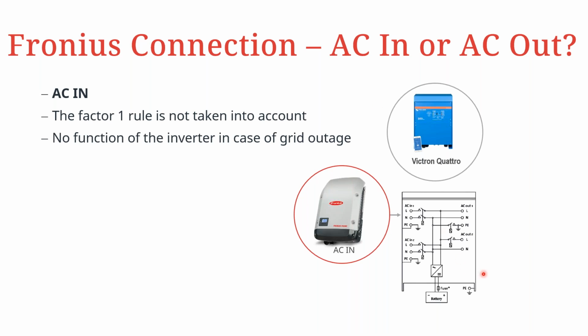So when it comes to the connection of the Fronius inverter to the Victron inverter, you have to decide whether you're going to connect it on the inside or the outside of the Victron inverter. So when you connect the Fronius inverter to the AC in of the Victron inverter, there is what we refer to as the factor 1 rule. Then this is not taken into account when you are sizing the PV inverter. The downside to this kind of connection is that when the grid fails, then the Fronius inverter also stops working.